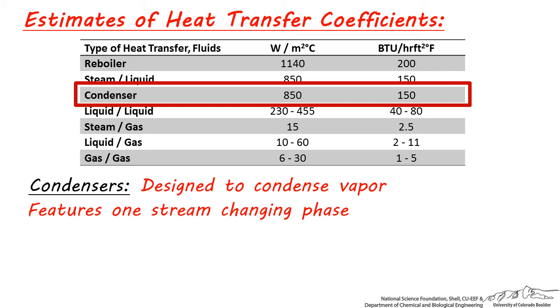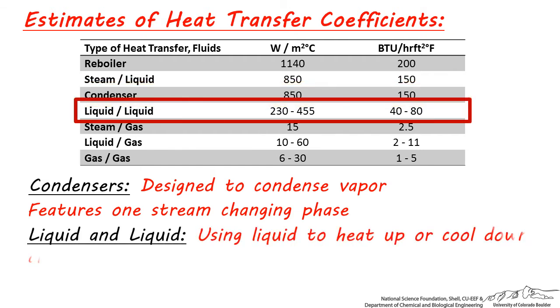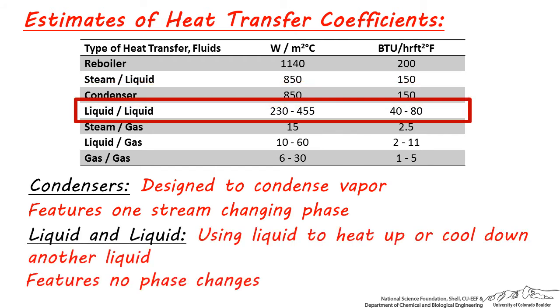We see a big drop between heat exchangers which feature latent or phase change heat transfer and simple heat transfer heat exchangers when we move to a liquid heating up or cooling down another liquid. Here no phase change is occurring — the heat transfer is simple conductive and convective. The range for coefficients is larger because the heat transfer is dependent on the velocity and type of fluids.